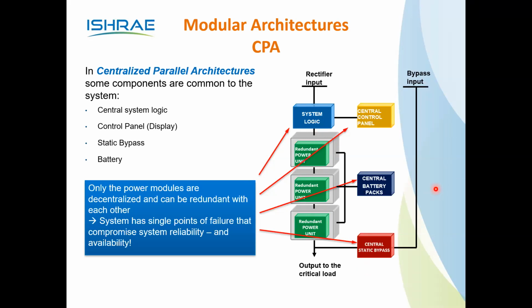But practically, if you ask me, the redundancy level is missing here. The redundancy is available only on the power unit side, not in the system logic. System logic is the main intelligent module; otherwise I would say it's the CPU. There is no redundancy here. The control panel, again, has no redundancy. The static bypass is common, no redundancy. Even if any one of these power units fails, say 80 kilowatt is the load, so three 40 kilowatt power units have been given, the other two power units will support the load.